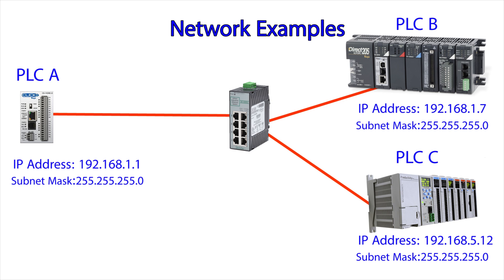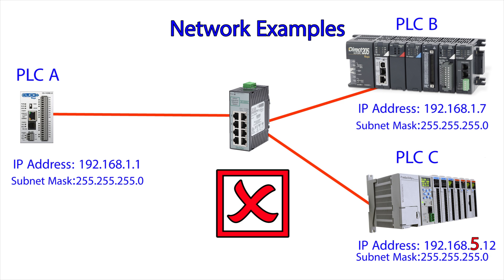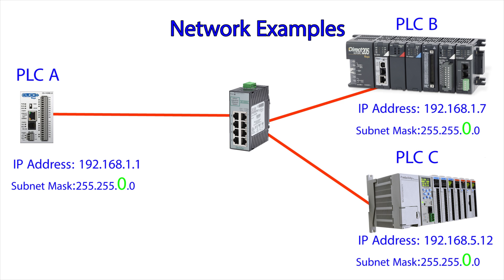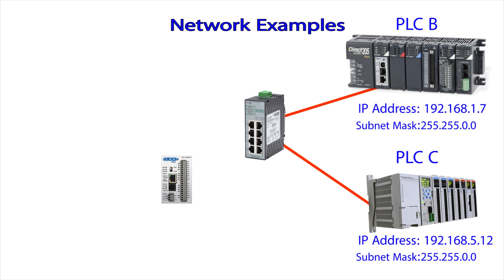Now let's add in PLC C to our switch. Will this PLC be able to talk with our other PLCs? No. We can see that the third group of PLC C's IP address does not match the other PLCs. How can we make all three of these devices talk to one another? Easy — we would just have to redefine the subnet mask of all these devices to be 255.255.0.0. Now all the devices can talk to one another. When the IP address and the subnet mask combine to allow devices to talk to one another, this is called a subnet.